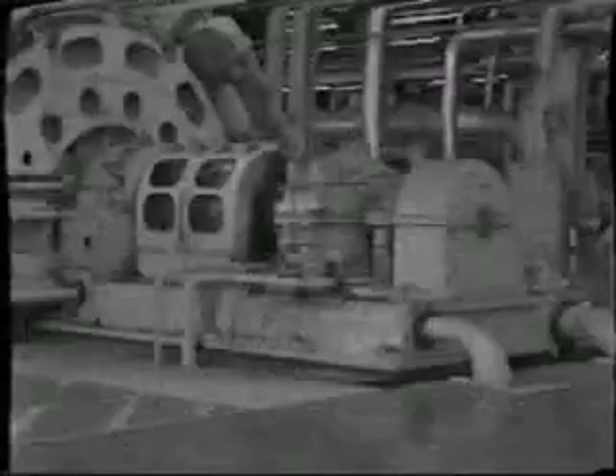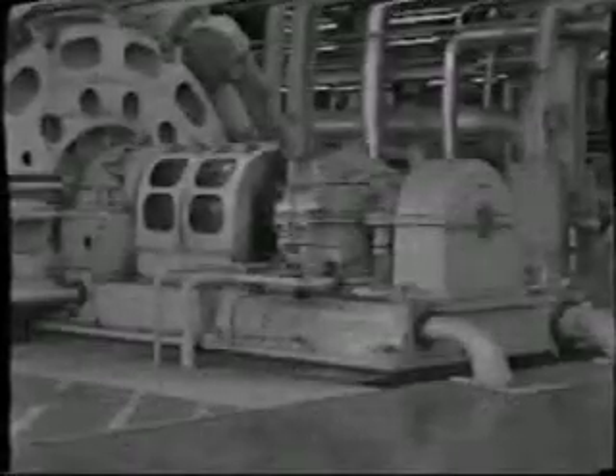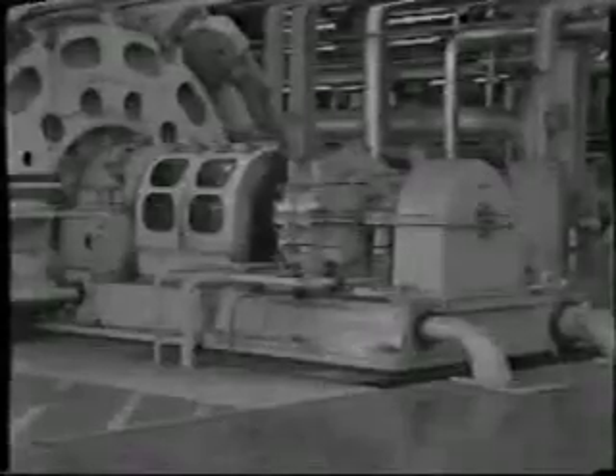As this tape deals specifically with generator protection, we will not be discussing prime mover problems or protection schemes. Indeed, this subject is very well covered in others of our video programs. When a generator is tripped from the system, its excitation system must also be de-energized by tripping the field breaker or equivalent. There are two basic methods of connecting the generator to the power system.